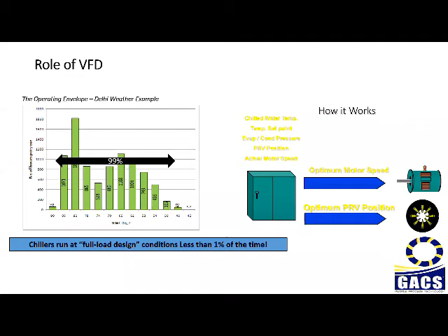So what does a VFD do? A VFD is a device which is used in a chiller for capacity control purposes. It regulates the motor speed and the refrigerant flow through the PRV in centrifugal chillers. And the VFD itself has an algorithm, or it should have a site based algorithm. There are OEMs who can provide a factory fitted VFD which can predict the loading pattern of the building, and that VFD will decide how the chiller can run in the efficient position. So those VFDs are completely synchronized with the machine, right?